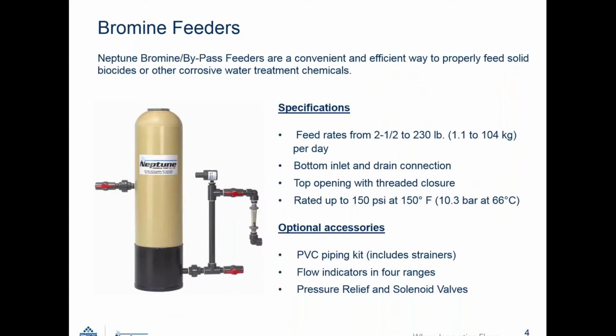We have bromine feeders. Bromine feeders are just like a bypass feeder. You're feeding through the water line into the system. It's a convenient way to properly feed solids, solid biocides, and corrosive water treatment chemicals. There's different types, feed rates, meaning how many tablets you can actually put into the vessel, anywhere from 2.5 to 230 pounds per day.